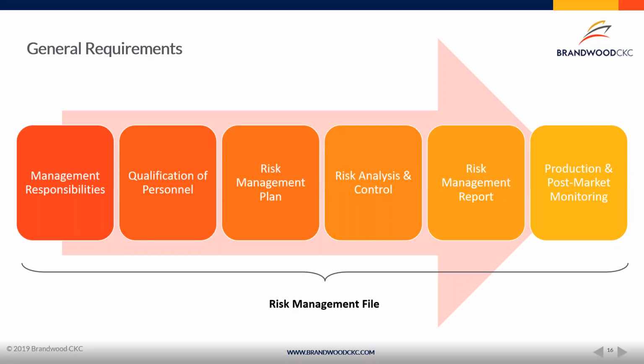The next step is you would create a risk management plan. This is the framework that you're going to create your entire risk management file based on. It is the starting point for the actual activities in design and development, to understand how you're going to evaluate the risk of your device. This is critical, because it will outline the steps you're going to take, the assumptions, the intended use, all of those things. So critically, you need to have that risk management plan locked down. We'll get into each of these individually in a couple more slides, but I just want to touch on them at a high level. The next one is risk analysis and control.